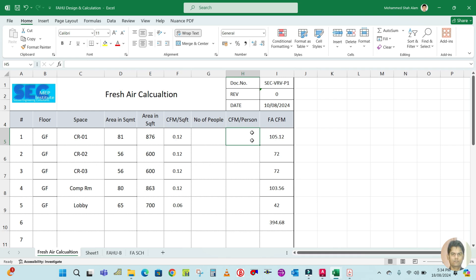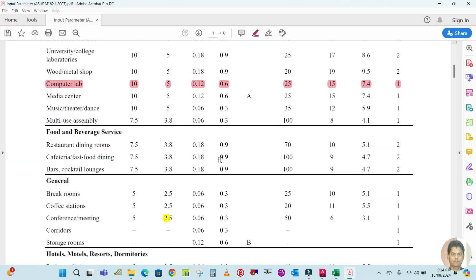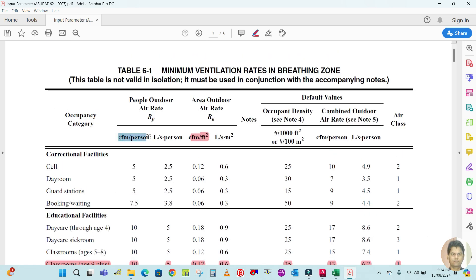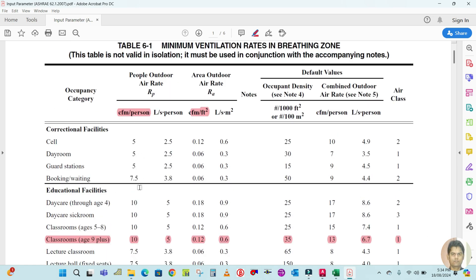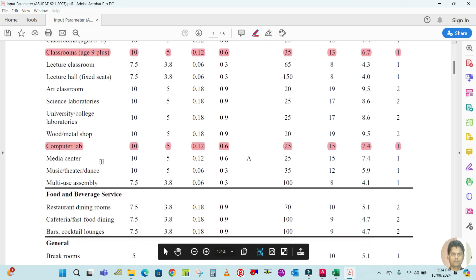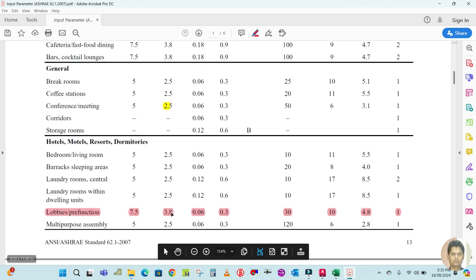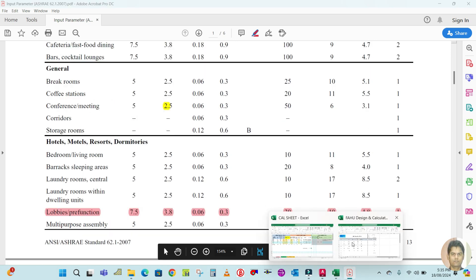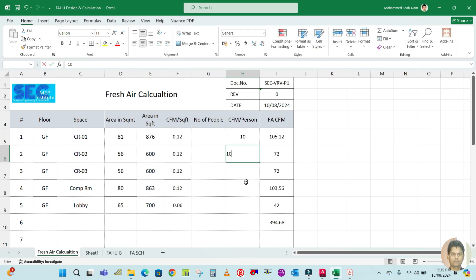Looking at the CFM per person column in the table: for classroom it is 10 CFM, for computer lab it is 10 CFM, and for lobby it is 7.5 CFM. Enter 10, 10, and 7.5 in the CFM per person column of the spreadsheet.